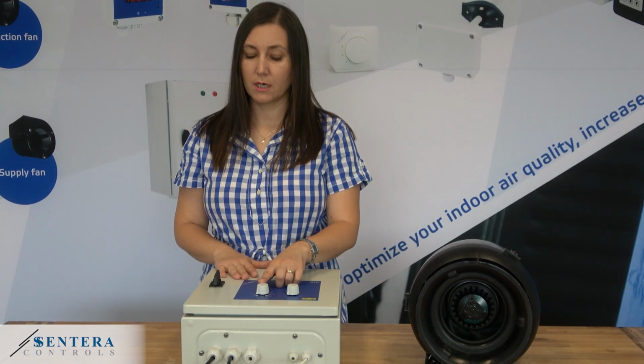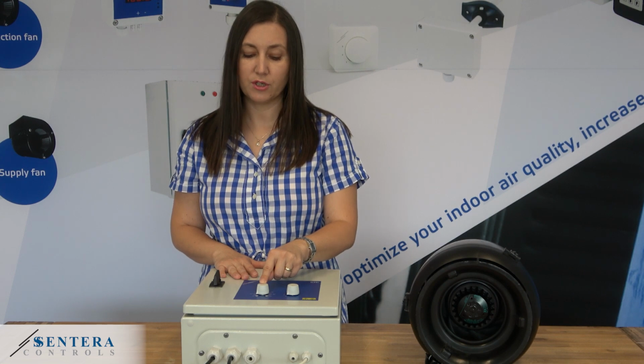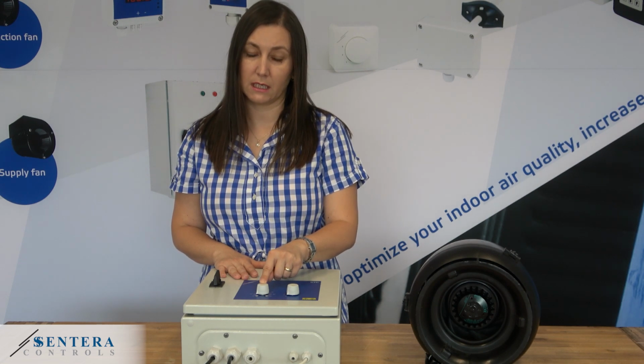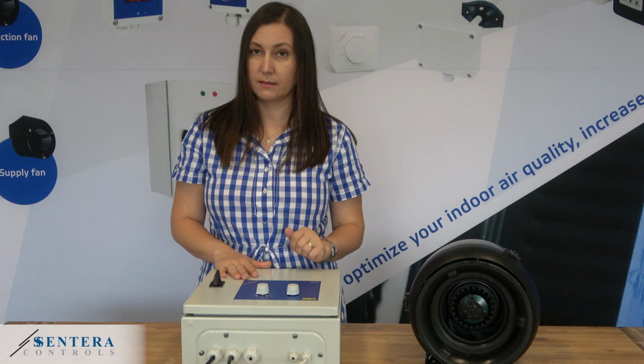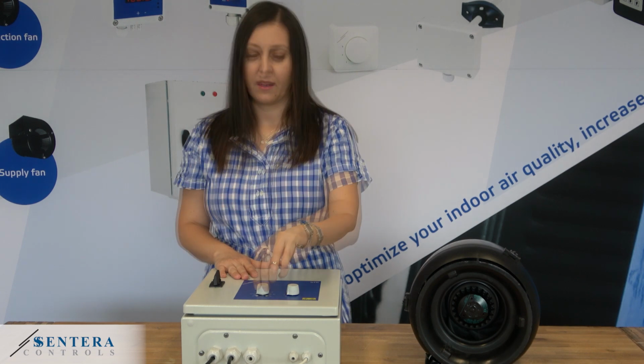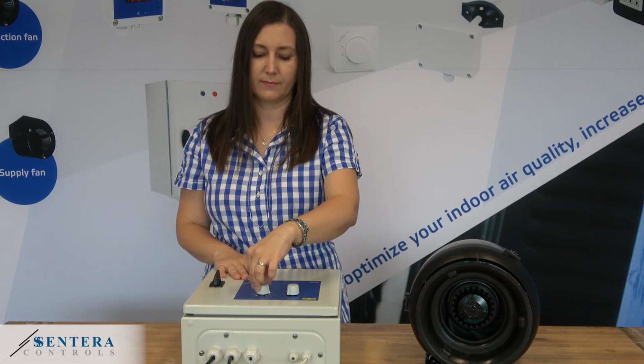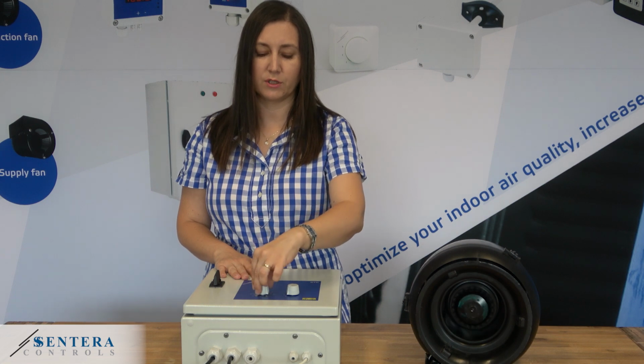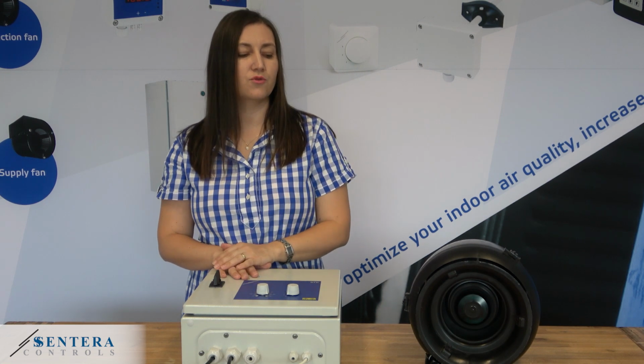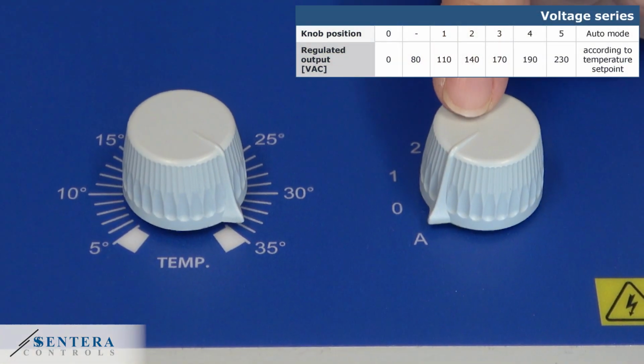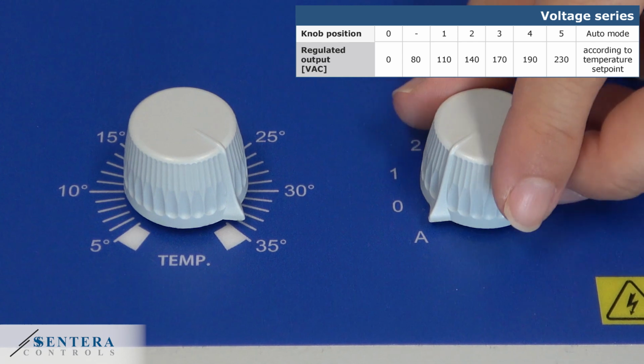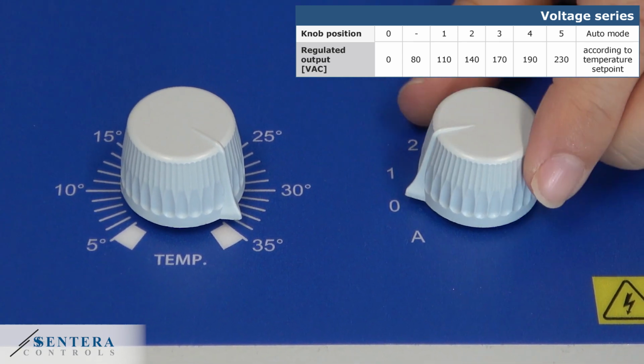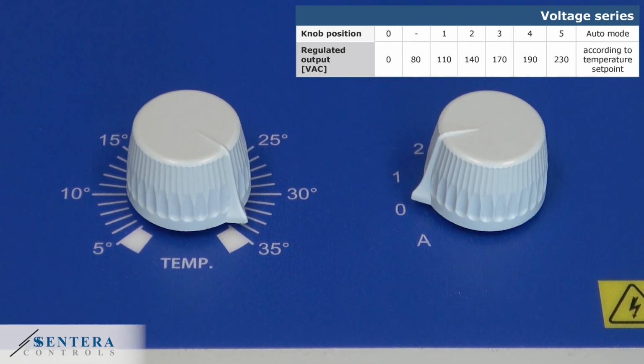Now our controller is supplied and the temperature set point is 5 degrees centigrade. Since the working mode is heating, the fan is not working because the temperature in the room is much higher. I turn the knob and change the set point to 35. The temperature in the room is lower, so the fan starts working. The controller is now running in automatic mode. I want to switch it off. And the fan stops working.